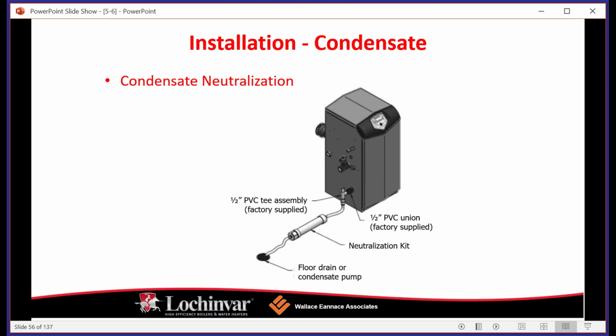Again, that's going to kind of be at the discretion of the installer. You can get a little pH test kit and test the outlet water, see how it's looking. Again, if it's coming out inert, your neutralization kit is still working, but if it's starting to trend towards the lower end of the pH scale, then you want to replace that neutralization media. Again, in the form of little pebbles.